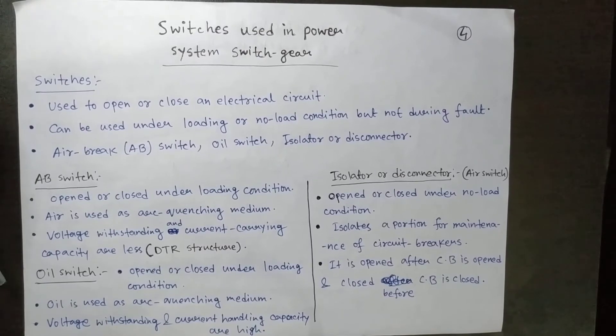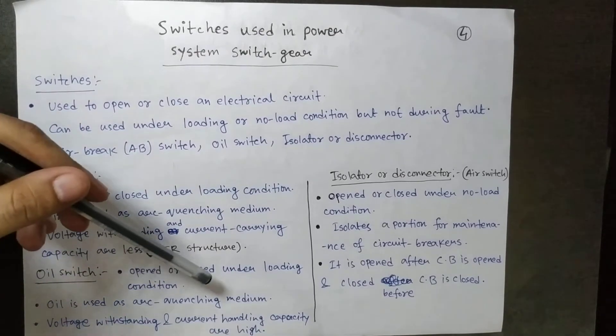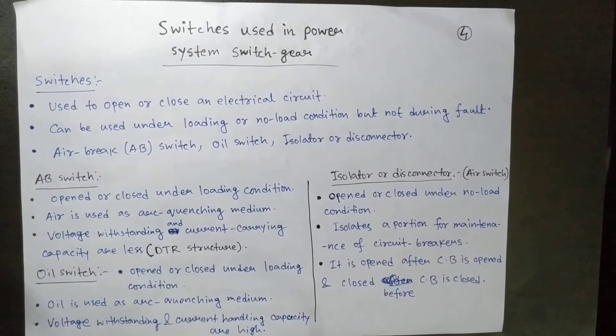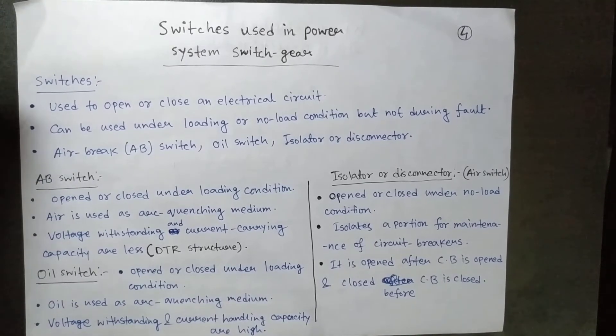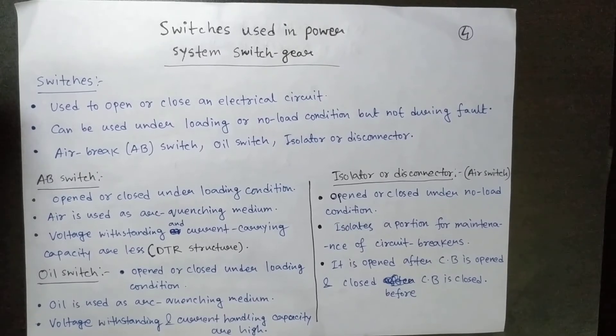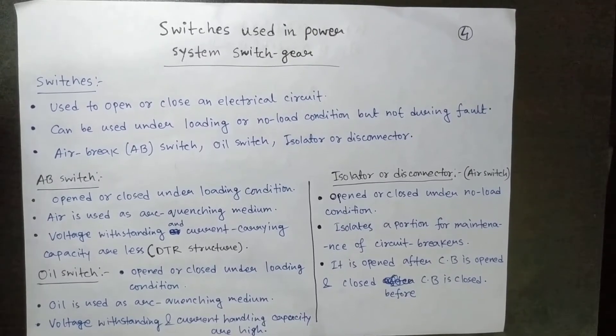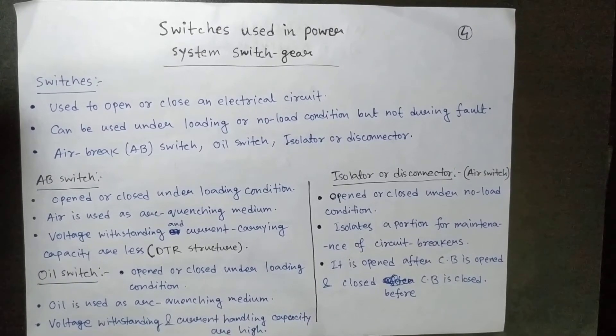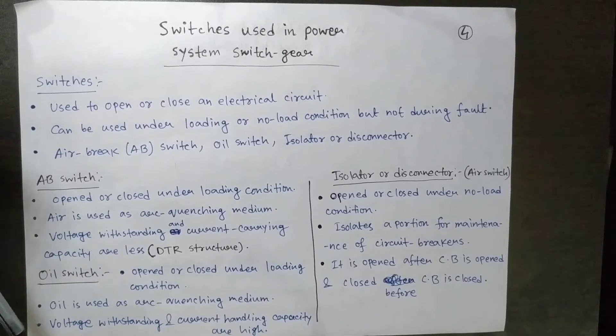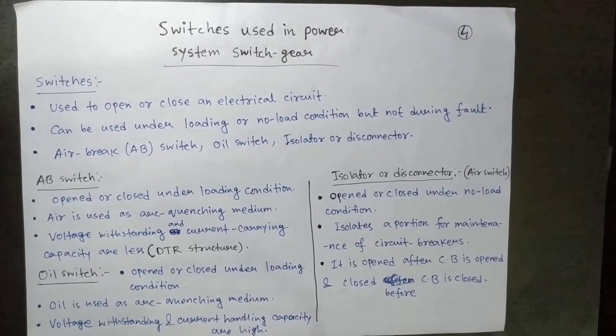When it comes to the oil switch, it is also opened or closed under loading condition, but here oil is used as the arc quenching medium. Because oil has a larger dielectric strength compared to air, the voltage withstanding capability for this kind of switch is higher compared to the AB switch.